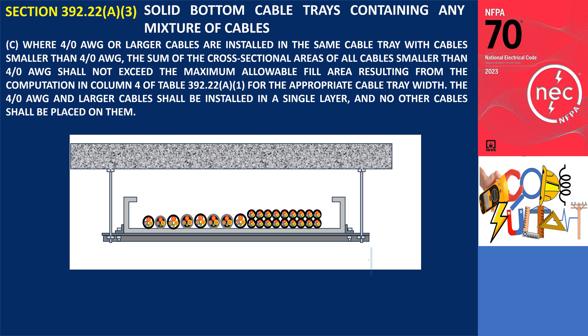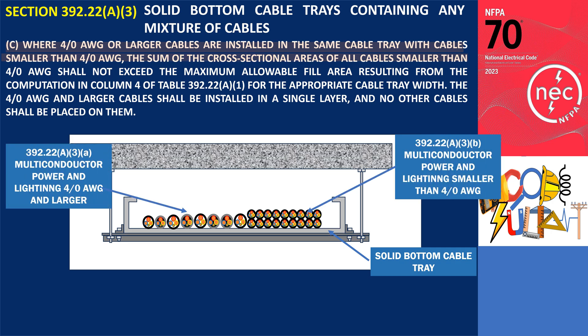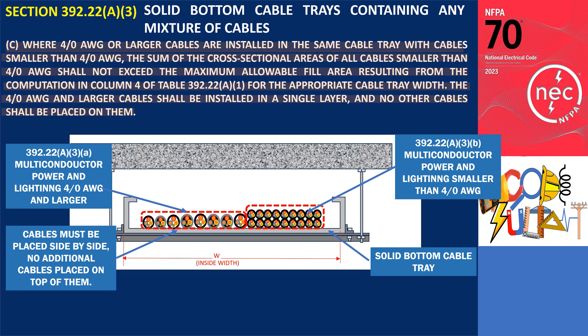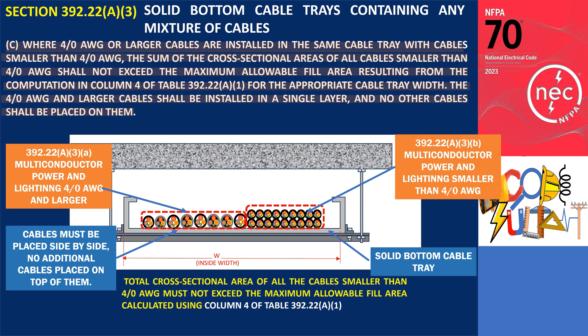Section 392.22(A)(3)(c) applies where 4-aught AWG or larger cables are installed in the same cable tray with cables smaller than 4-aught AWG. The sum of the cross-sectional areas of all cables smaller than 4-aught AWG shall not exceed the maximum allowable fill area resulting from the computation in Column 4 of Table 392.22(A)(1) for the appropriate cable tray width. The 4-aught AWG and larger cables shall be installed in a single layer, and no other cables shall be placed on them. This subsection is the combination of subsections 392.22(A)(3)(a) and (b), where the cable tray contains a mix of 4-aught AWG or larger cables and cables smaller than 4-aught AWG.